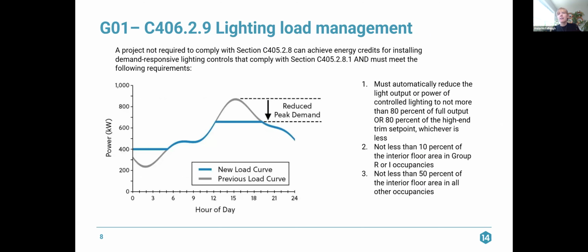Credit G01, lighting load management. So any project that is not required to comply with section C405.2.8, which we'll go through in the next slide, can achieve energy credits for installing demand responsive lighting controls that comply with C405.2.8.1. So that's how the controls work, and they must meet the following requirements. They must automatically reduce the light output or power of controlled lighting to not more than 80% of the full output.